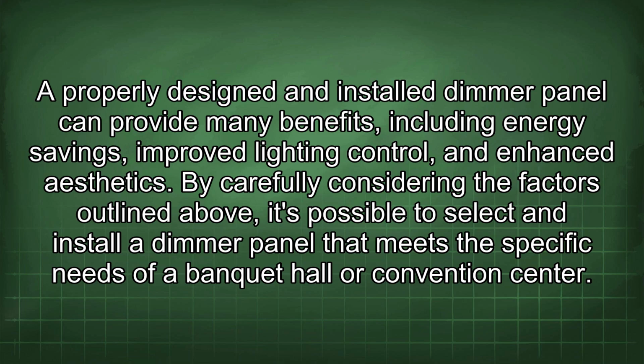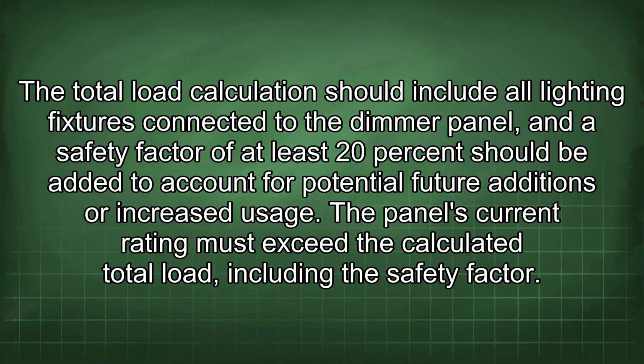By carefully considering the factors outlined above, it's possible to select and install a dimmer panel that meets the specific needs of a banquet hall or convention center. The total load calculation should include all lighting fixtures connected to the dimmer panel, and a safety factor of at least 20% should be added to account for potential future additions or increased usage.